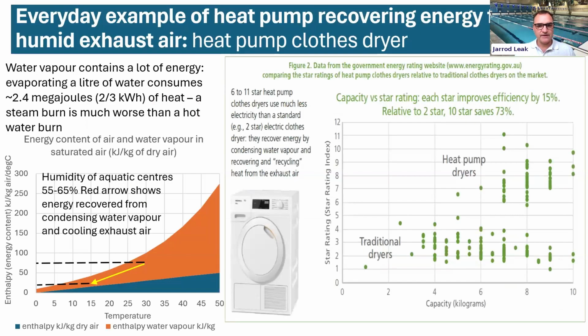And then the final one I'll add: there's so much more energy in the vapor. That means whilst a thermal wheel is often employed to recover energy, a thermal wheel is fine, but that's only getting you a small portion of what's available. If you look at a company called Air Change and their Pool Pack Plus system, that helps recover heat, latent heat, and that will certainly be a big boost for you. Feeding that back exactly when you need it on those colder days, that's when you want to be as efficient as possible, and that's when that sort of system will really pay off.